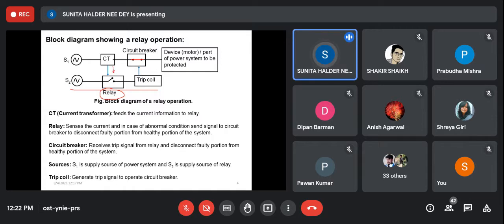Then there will be a secondary system, this one, where there is a relay. The relay will sense the current from the CT, and it will give the signal to the trip coil depending on the abnormality of the system. Now you must remember, the relay is a low power device, so system 2 is low power, and S1 is the power system voltage or power system source. So obviously, what are the main components of the block diagram of a relaying operation? Relay, circuit breaker, along with source, CT and trip coil. The trip coil is included within the circuit breaker. So for relaying operation, we need a CT, we need a relay that will give the supply to the trip coil, and we need a circuit breaker.